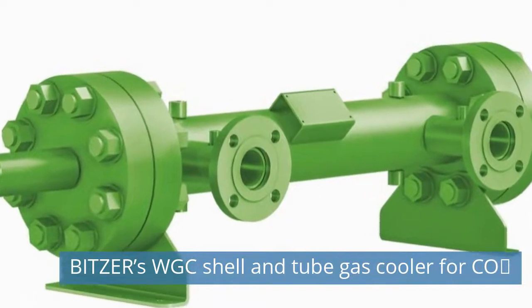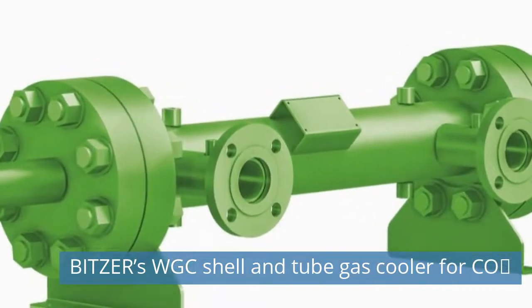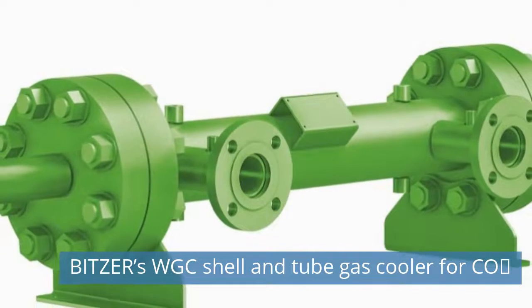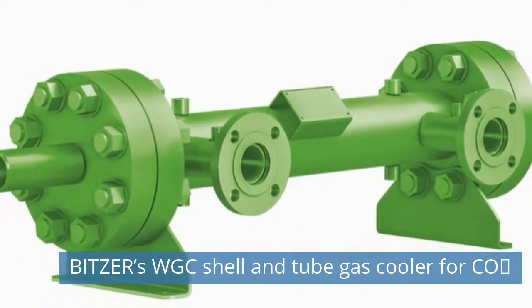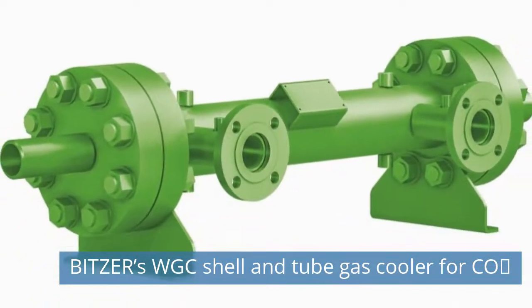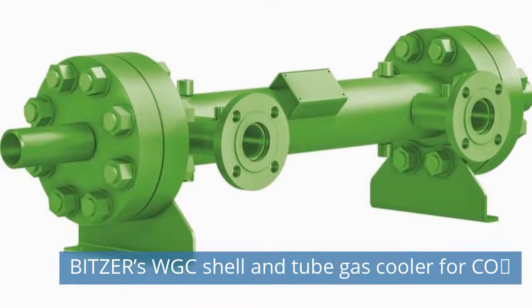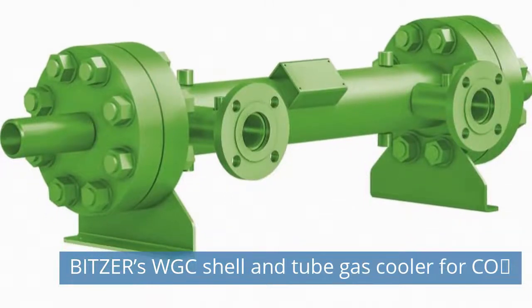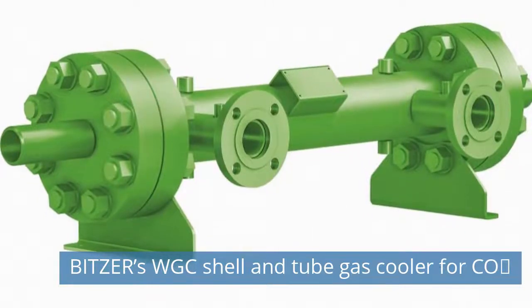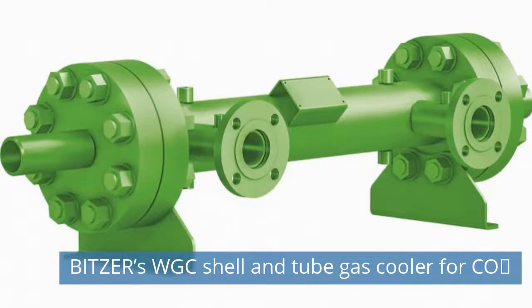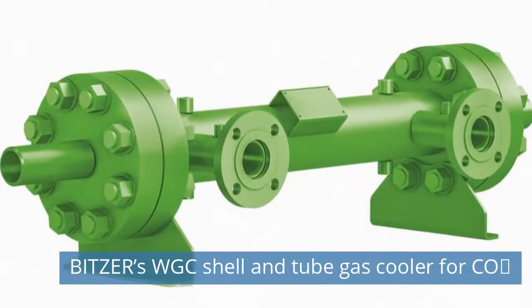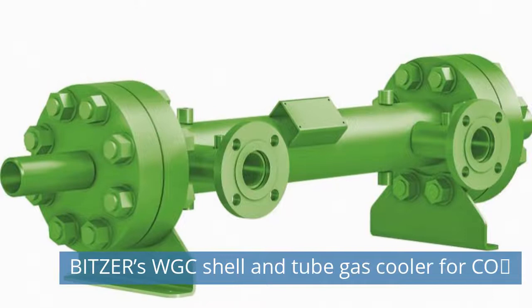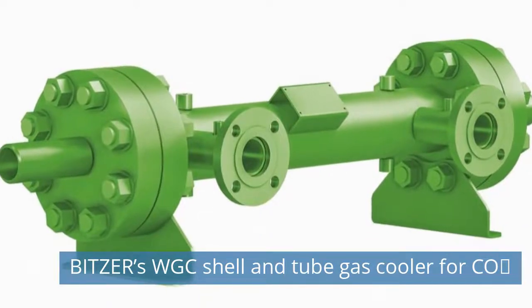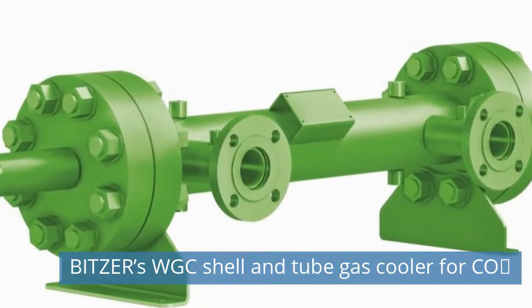The BITZER WGC is a new family of liquid-cooled heat exchangers with several sizes and lengths, typically used in commercial and light industrial refrigeration. This heat exchanger concept can be used as a gas cooler, a heat recovery exchanger, or a condenser, all in transcritical CO2 applications. One WGC model can thus operate in different modes within the same system, depending on the working conditions of the moment.